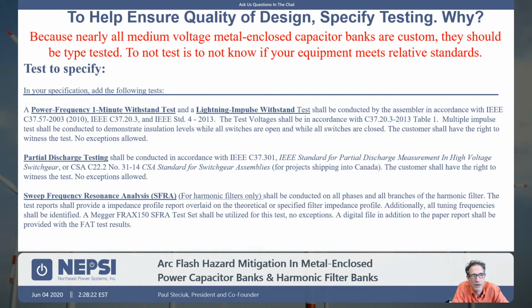The other thing to think about is testing. Okay, if you are in a position where you're specifying metal-enclosed capacitor banks and harmonic filter banks, demand testing. Do not trust that the supplier of the equipment has built it correctly. I mean, let's face it, if you build a piece of equipment that's designed for 95 kV BIL, but you don't impulse test it, how do you really know that it's designed and built to 95 kV BIL? You're taking the word of a design engineer, that's all.